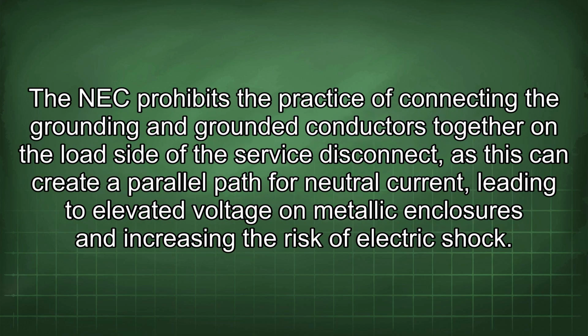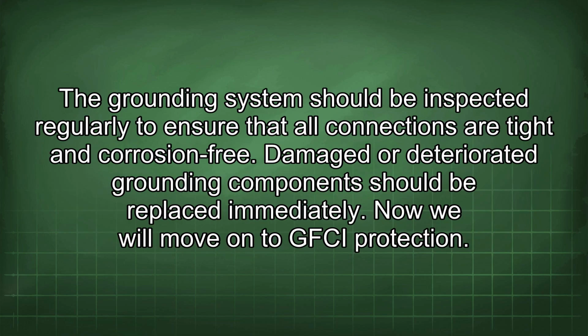The NEC prohibits the practice of connecting the grounding and grounded conductors together on the load side of the service disconnect, as this can create a parallel path for neutral current, leading to elevated voltage on metallic enclosures and increasing the risk of electric shock. The grounding system should be inspected regularly to ensure that all connections are tight and corrosion-free. Damaged or deteriorated grounding components should be replaced immediately.